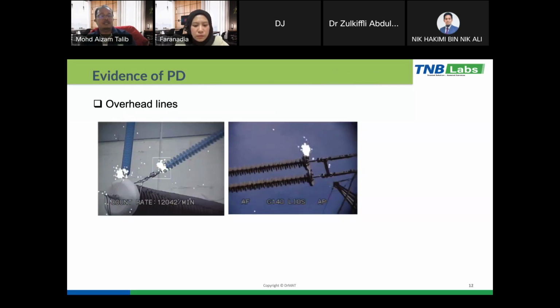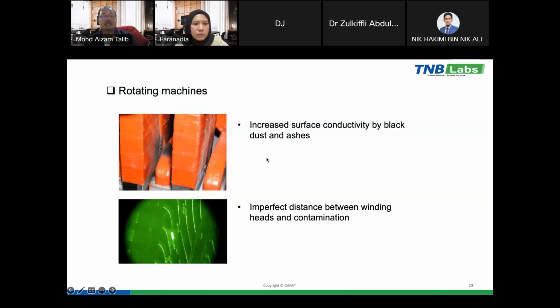So these are some examples of evidence of present PD at different assets. Through this corona camera, we can see the partial discharge activity at this overhead line disconnector. And then we can see that when there is a presence of PD, it will increase the surface conductivity. And then we can see there is black dust and ash in the stator windings. And also when we have imperfect distance between the winding heads and the presence of contaminations, it can also cause the presence of partial discharge.